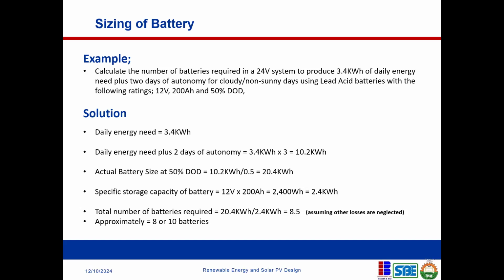When you look at the tech sheet of batteries, one of the things you will likely see is the number of cycles that battery can go. Number of cycles means the number of times you can fully charge that battery and discharge that battery. After that number of cycles, the battery capacity will reduce, sometimes to maybe about 80%, depending. But you're going to see this in the tech data sheet of a battery.